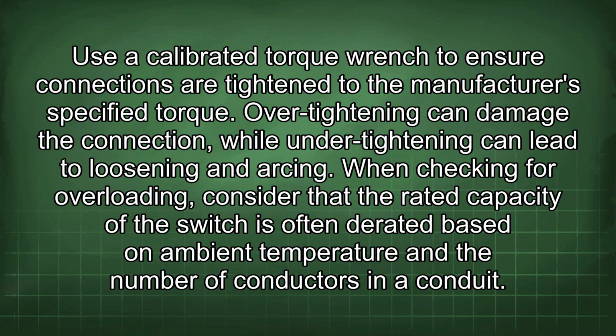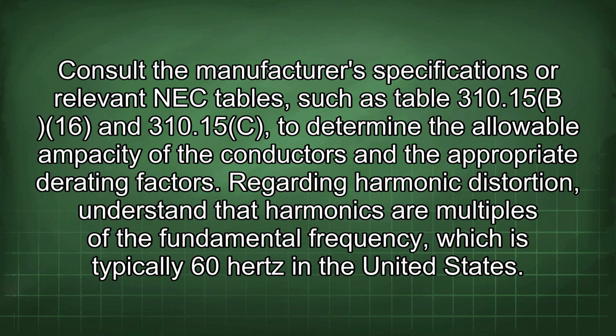When checking for overloading, consider that the rated capacity of the switch is often derated based on ambient temperature and the number of conductors in a conduit. Consult the manufacturer's specifications or relevant NEC tables, such as Table 310.15(B)(16) and 310.15(C), to determine the allowable ampacity of the conductors and the appropriate derating factors.